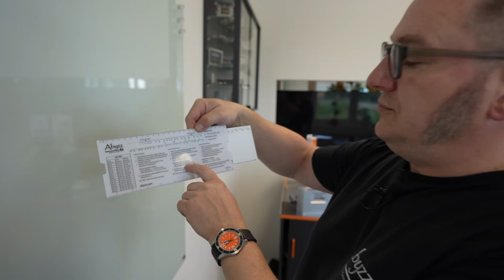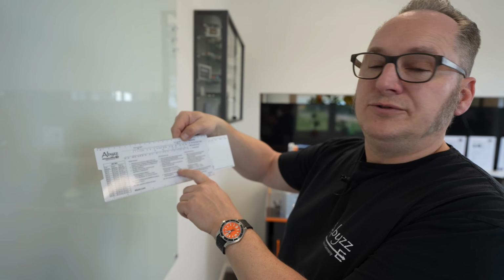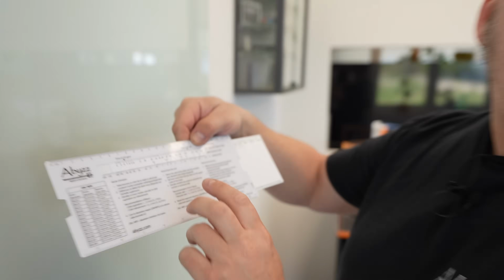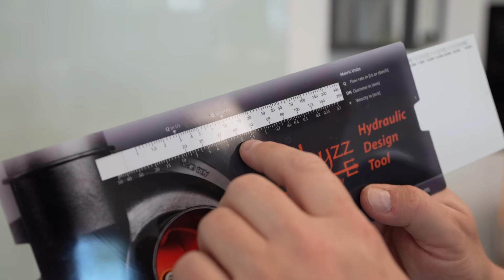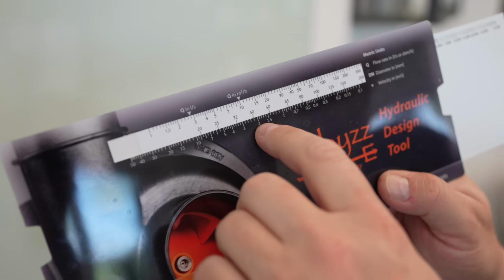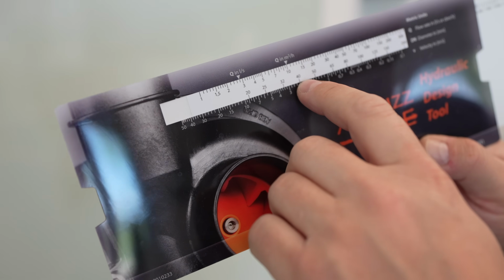So for the pressure side, we're not to exceed 1.5 to 2 meters per second, which is 5 to 6.5 feet per second. On the suction side, you should be at 1 to 1.5 meters per second, which is 3 to 5 feet per second. So if you go to the velocity and you see 2 meters per second, that's actually 40 is not enough. Even though the outlet of the pump might be 40, if you check the manual, it'll say, please make sure you have the right pipe diameters.